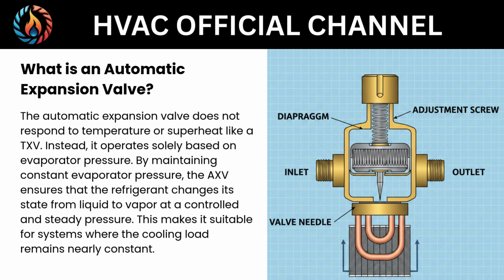The automatic expansion valve does not respond to temperature or superheat like a TXV. Instead, it operates solely based on evaporator pressure. By maintaining constant evaporator pressure, the AXV ensures that the refrigerant changes its state from liquid to vapor at a controlled and steady pressure. This makes it suitable for systems where the cooling load remains nearly constant.